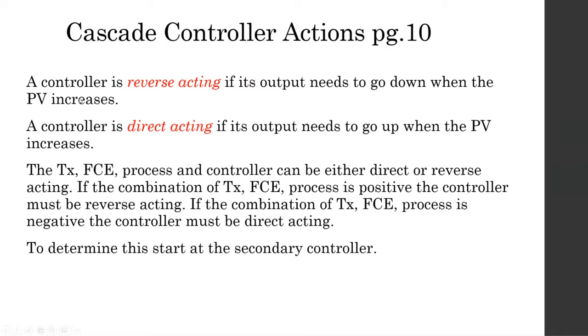So quick review here. Controller is reverse acting if its output needs to go down when the PV increases. So if the input goes up and the valve closes, it's reverse acting. And the controller is direct acting if its output needs to go up when the PV increases. So again, not going to try to confuse you with that. You should understand that by now.